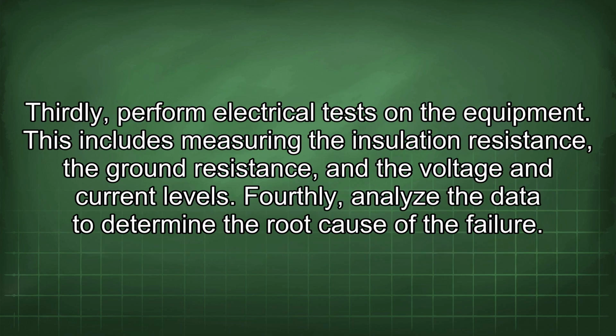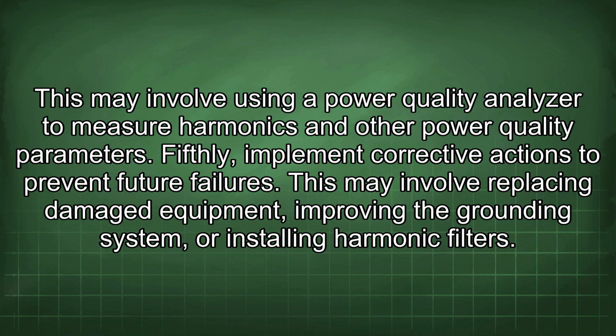Thirdly, perform electrical tests on the equipment. This includes measuring the insulation resistance, the ground resistance, and the voltage and current levels. Fourthly, analyze the data to determine the root cause of the failure. This may involve using a power quality analyzer to measure harmonics and other power quality parameters. Fifthly, implement corrective actions to prevent future failures. This may involve replacing damaged equipment, improving the grounding system, or installing harmonic filters.